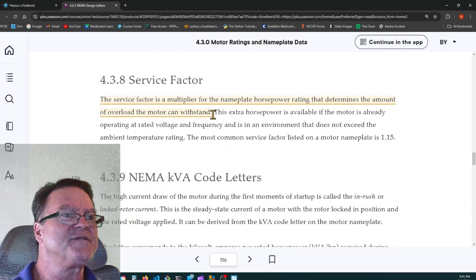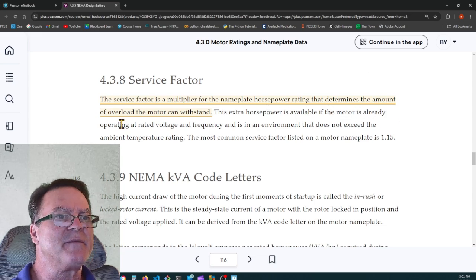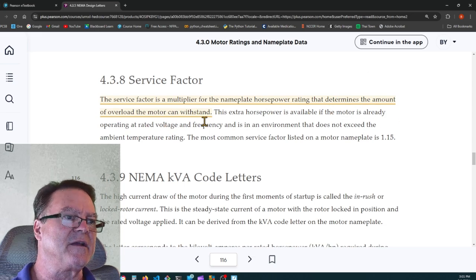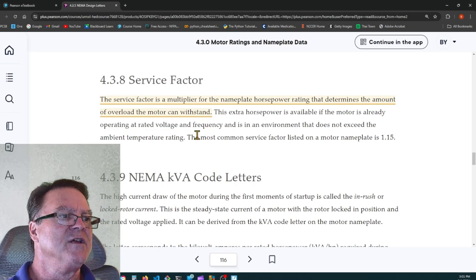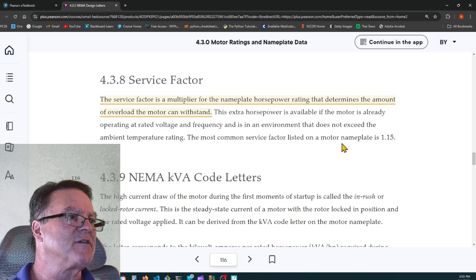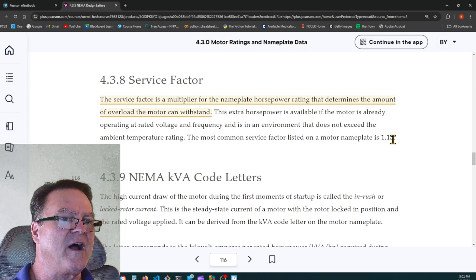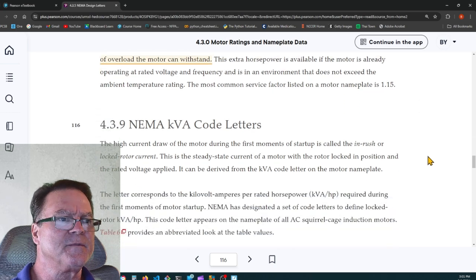Service factor. The service factor is a multiplier for the nameplate horsepower rating that determines the amount of overload the motor can withstand. So the most common service factor listed on a motor nameplate is 1.15. And I think you could take it to 125%.